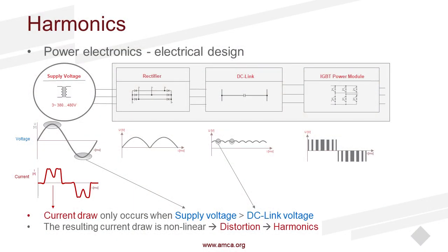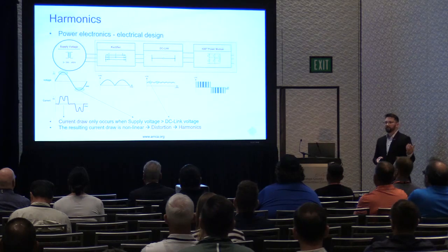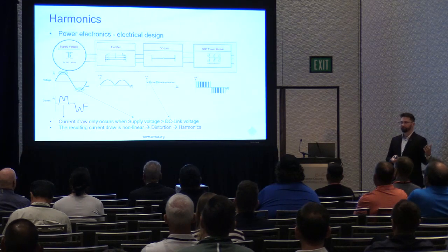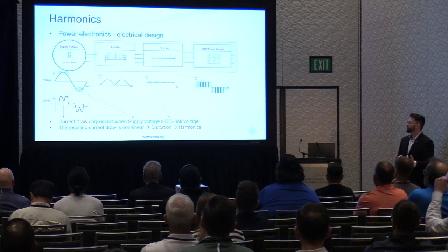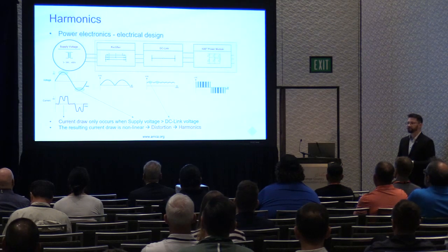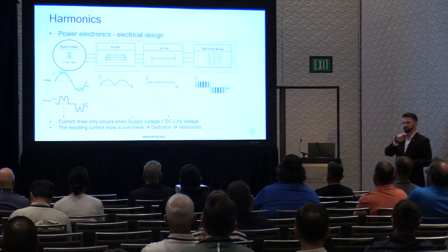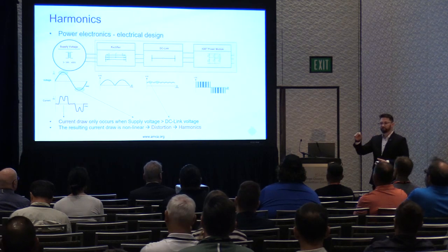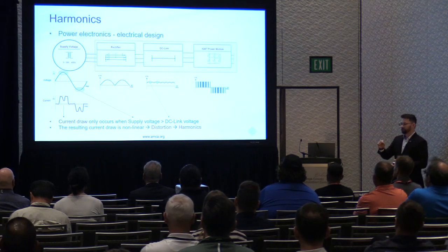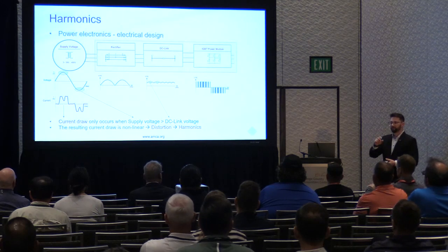So we can look at a simple VFD or EC motor. There's 3 typical components. You have your rectifier, your DC link, and your IGBT power module. In your rectifier, you're taking in your sinusoidal voltage wave. You're converting it to a DC voltage, so cutting it, and so now you have a linear voltage, but it has some humps, some dips. And so with that, it goes into your DC link, and now you're trying to reduce all of those ripples and make it as linear as possible.